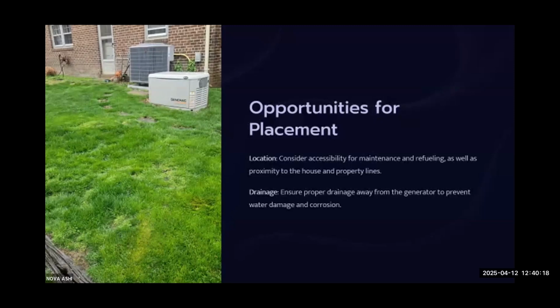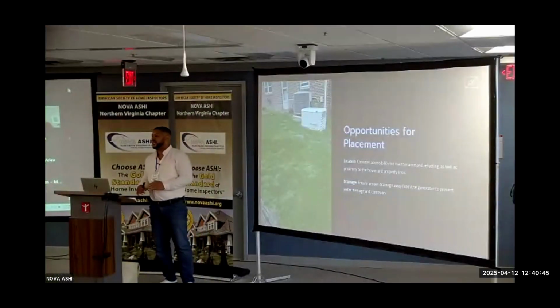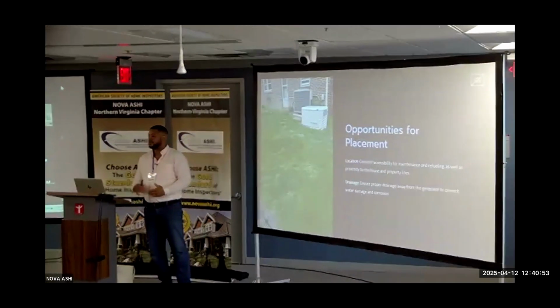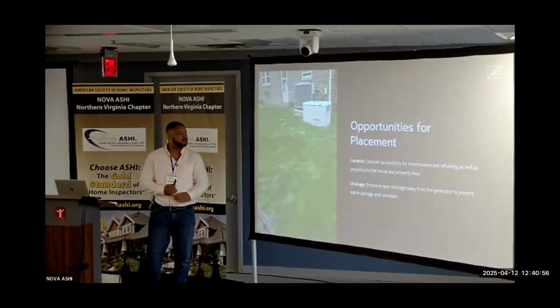With generators, you want the exhaust side away from the breaker side, and at least 5 foot or greater away from any windows, doors, or vents of that nature. As you see this AC unit, you want the generator at least 3 foot away from it. It's not that the AC unit's duct work travels back into the home, it's just for working clearance for the AC and the service techs for both the generator and the AC unit.